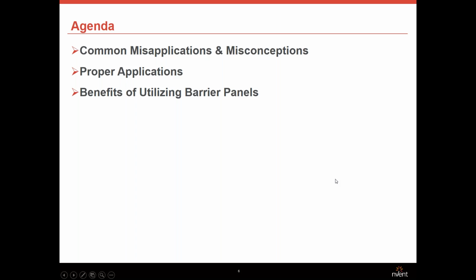In today's presentation, we'll be looking at common misapplications and misconceptions. We'll look at proper applications, and we'll look at the benefits of utilizing barrier panels. So when we talk about what barrier panels are not, first thing I want to say is barrier panels are not arc flash containment. In the event of an arc flash incident, copper wire can vaporize, expanding up to 67,000 times. The resulting pressure wave would push out through the areas of least resistance.